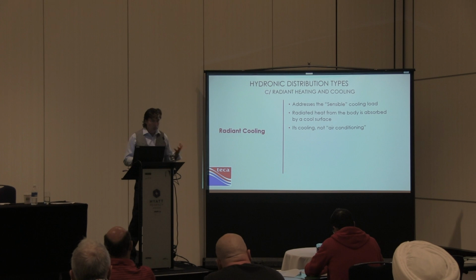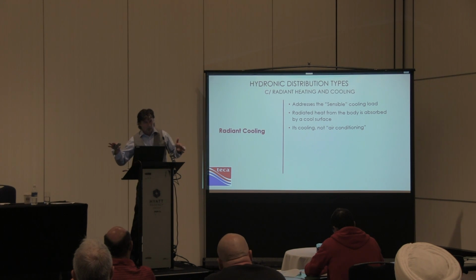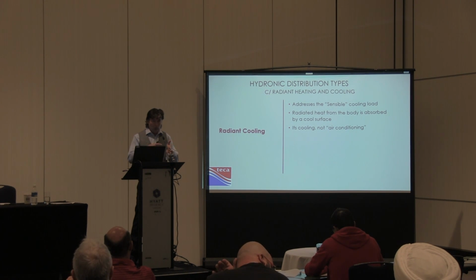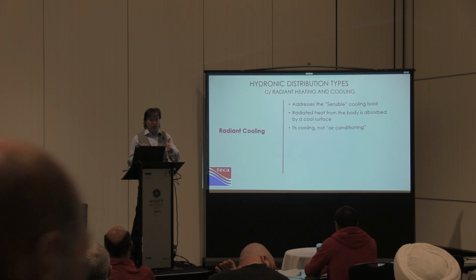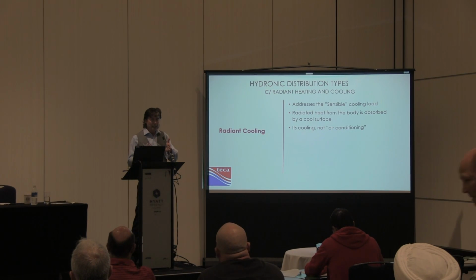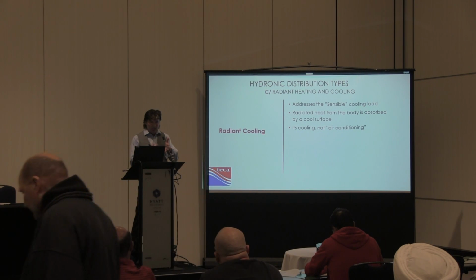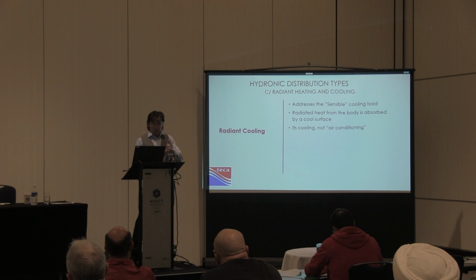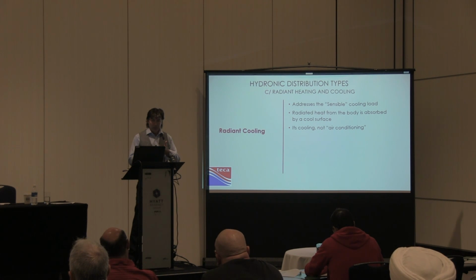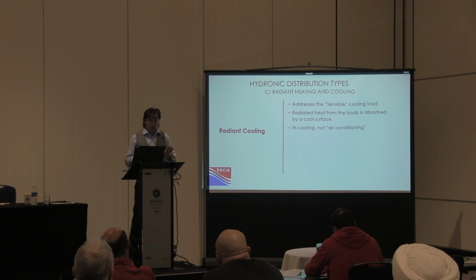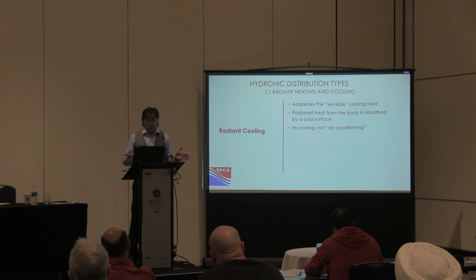So when you're in air conditioning mode, your classic air conditioner, what have you got? You've got warm air that circulates on the return air. It's say 80 degrees, and it comes back into the return air, goes over your cold refrigerant coil. And it's at that point, where that warm, moist air is, that you deal with the latent load. The moisture that's in the air, as that air cools, condenses on the evaporator coil, and that drips off down the drain as moisture. So you've actually removed the moisture from the air, or a good chunk of it. And for a lot of people, that's the uncomfortable bit, particularly if you're in Florida or in Toronto, etc. Here, not so bad. Our latent load is not so bad, but nonetheless, radiant cooling deals with none of that.